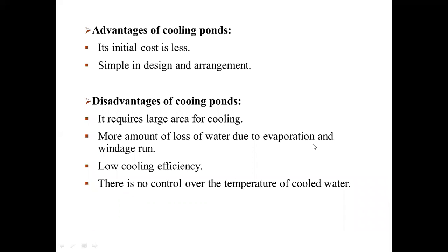Now, what are the advantages and disadvantages of the cooling pond? Initial cost is very less and very much simple in design and arrangement. But disadvantages are that it requires large area for cooling, more amount of loss of water due to evaporation and windage, very low cooling efficiency, and there is no control over the temperature of cooled water.